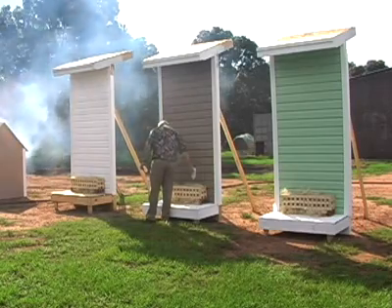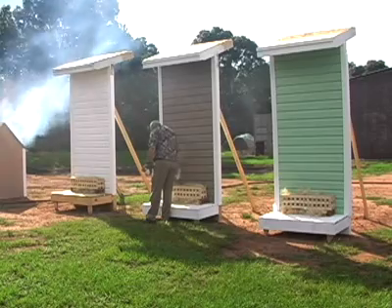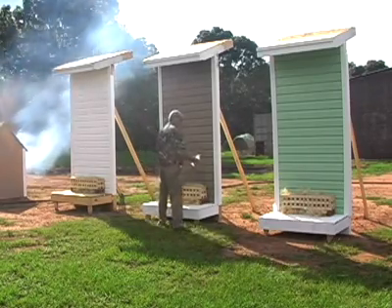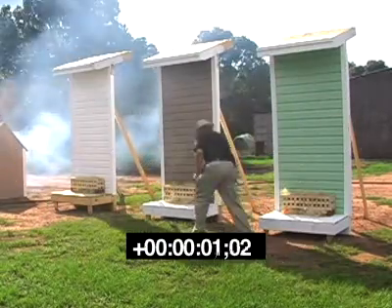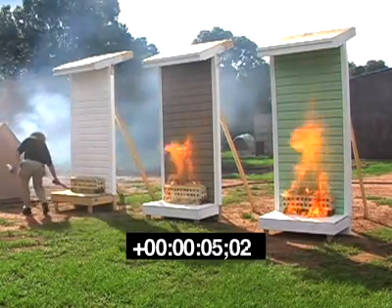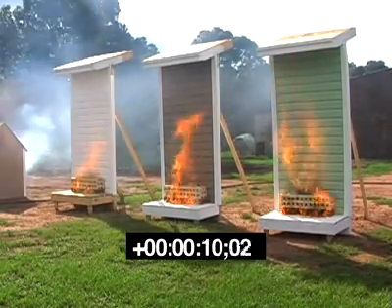The simulated fuel source for all three panels is a 20-pound wood crib with additional excelsior filler, providing a fuel source matching the criteria of the Factory Mutual 4880 room corner test. The sources of ignition are identical amounts of alcohol, and the actual ignition timing is very near simultaneous.